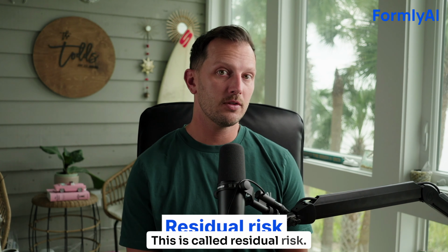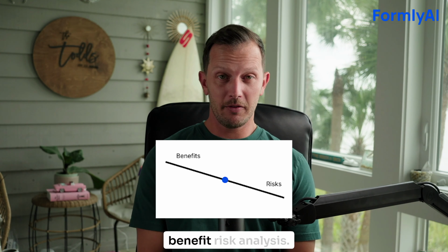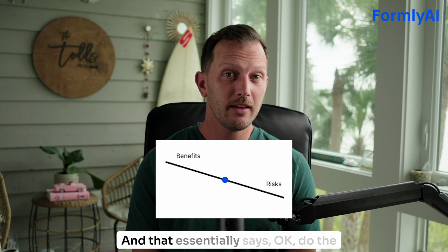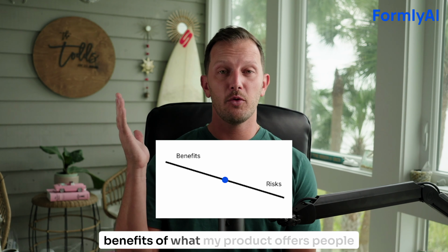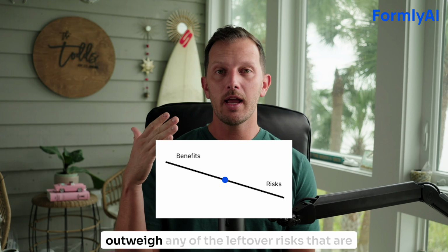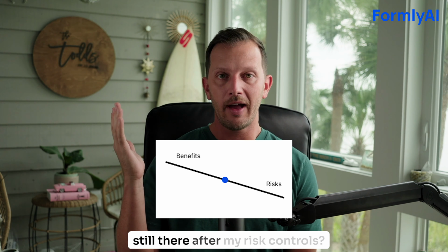So once you finish your risk analysis, essentially you're going to have leftover risk. This is called residual risk. Then you're going to do what's called a benefit risk analysis. And that essentially says, okay, do the benefits of what my product offers people outweigh any of the leftover risks that are still there after my risk controls?